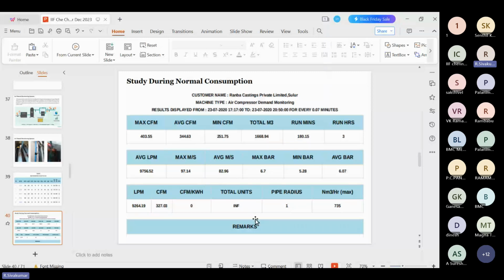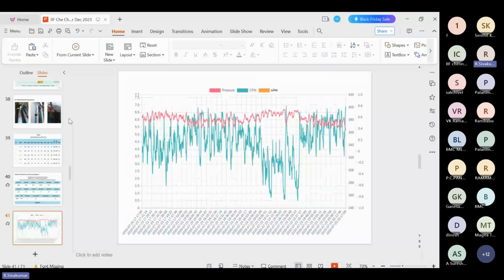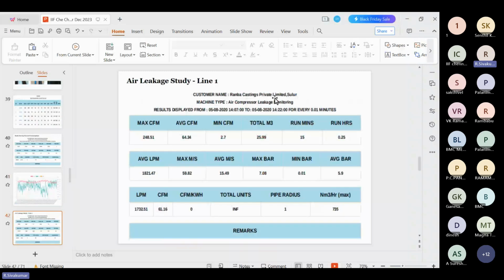All these things are taken, and I put my power quality analyzer at the input so that we can arrive at the kilowatt per CFM. This is the trend in graphical form. The red color indicates the pressure level and green indicates the CFM level. If the energy meter is also incorporated, then you can monitor the kW also. So you can see pressure, CFM, that means airflow, as well as the energy consumption in the same manner. The same for the study of line 1, what is the maximum and the minimum.